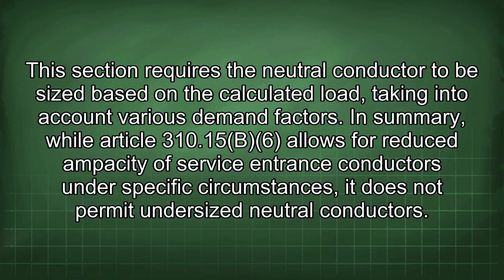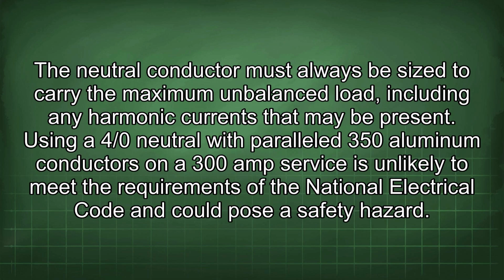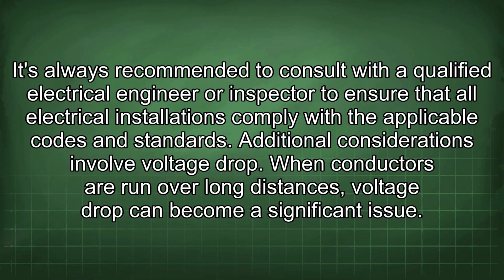In summary, while Article 310.15(B)(6) allows for reduced ampacity of service entrance conductors under specific circumstances, it does not permit undersized neutral conductors. The neutral conductor must always be sized to carry the maximum unbalanced load, including any harmonic currents that may be present. Using a 4/0 neutral with parallel 350 aluminum conductors on a 300 amp service is unlikely to meet the requirements of the National Electrical Code and could pose a safety hazard. It's always recommended to consult with a qualified electrical engineer or inspector to ensure that all electrical installations comply with the applicable codes and standards.